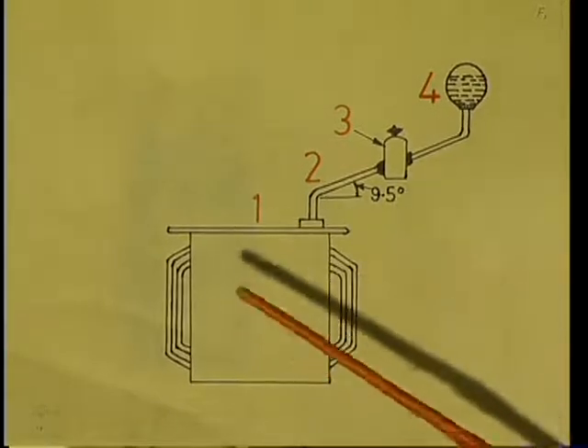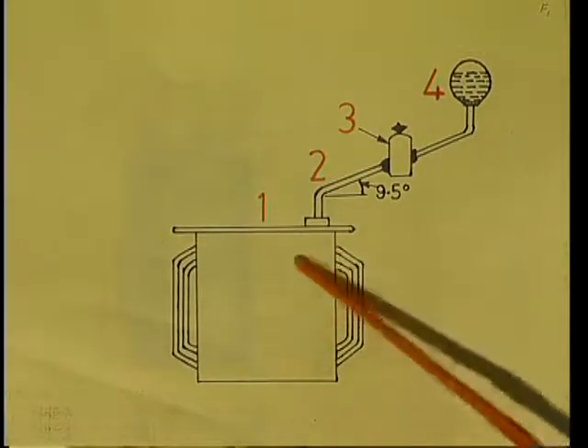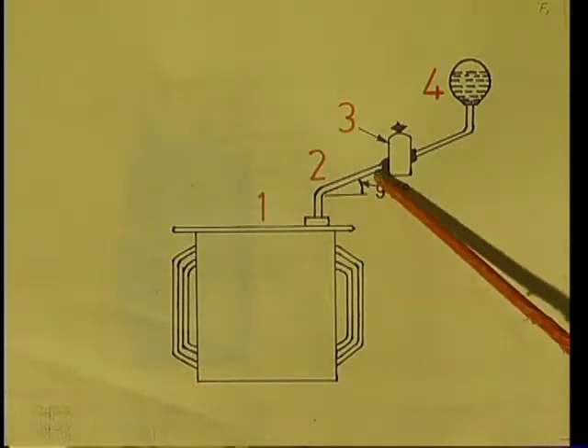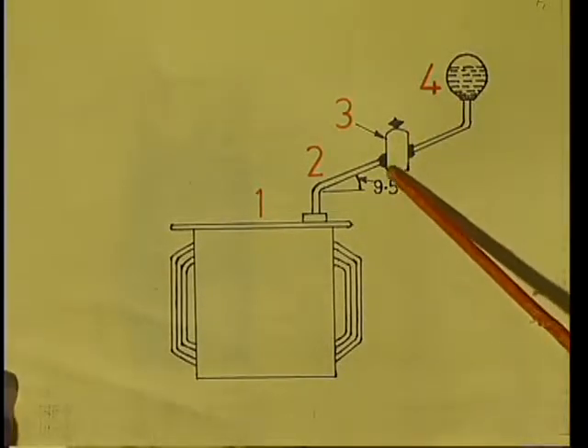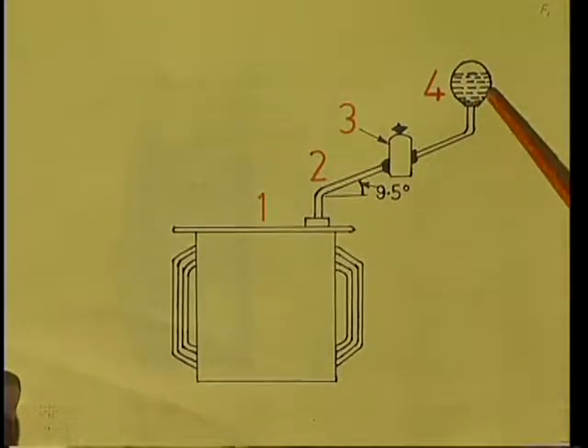The Buchholz relay is a gas-operated relay. It is installed between the pipe connecting the main transformer tank to the conservator. Buchholz relays are used on transformers of rating above 750 kVA. The connection consists of: (1) the main transformer tank, (2) the connecting pipe, (3) the Buchholz relay installed in between, and (4) the conservator.